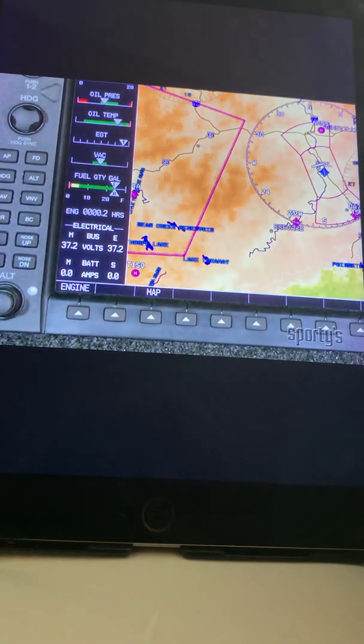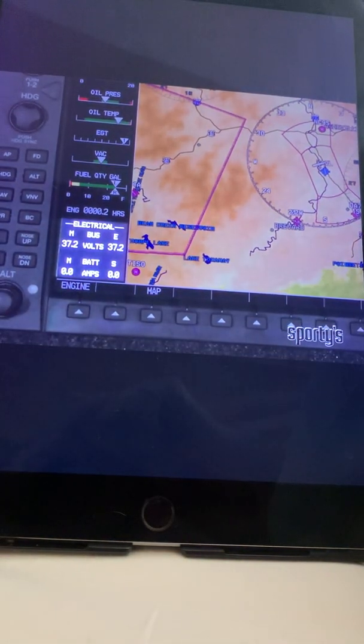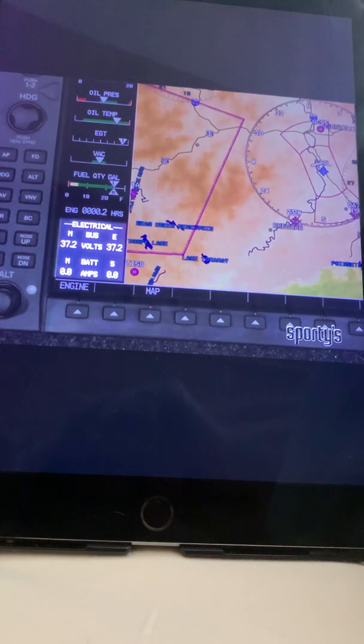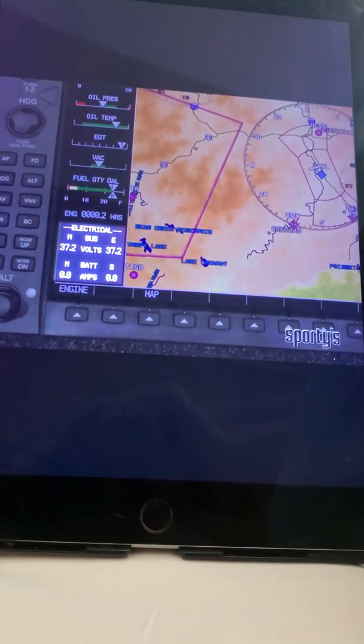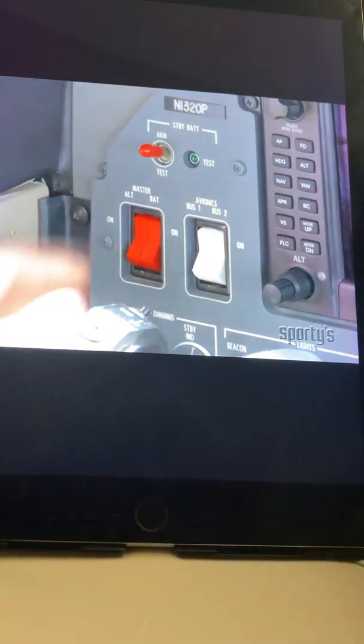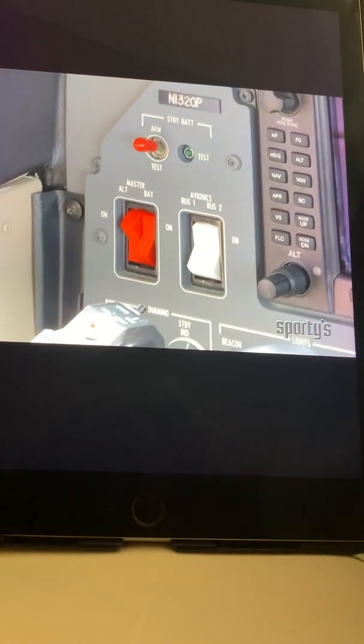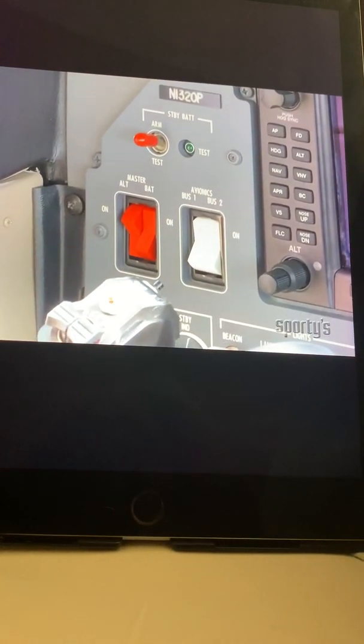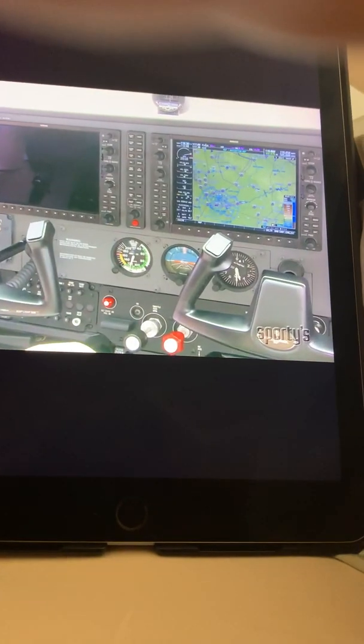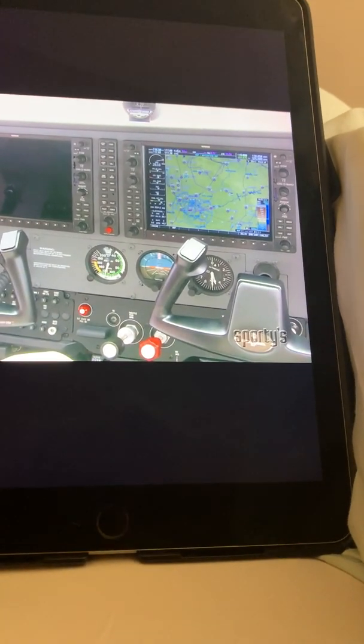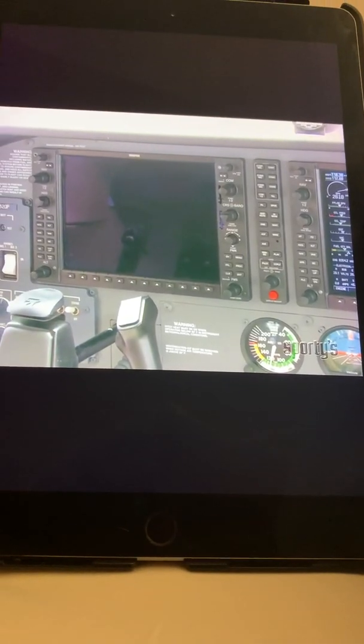It is possible to experience a situation in which the alternator produces too much voltage. This is called a runaway alternator. You want to react in essentially the same way as you did for an alternator out situation. Possibly one or both of your LCDs could fail. It's most likely that only one would fail at a time.